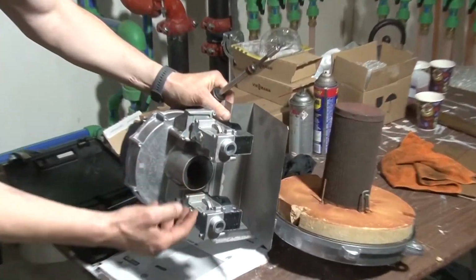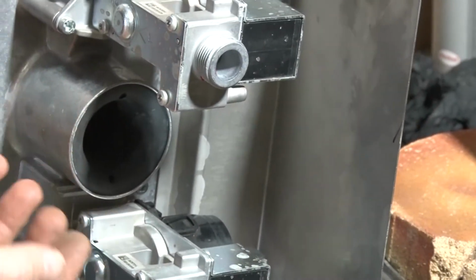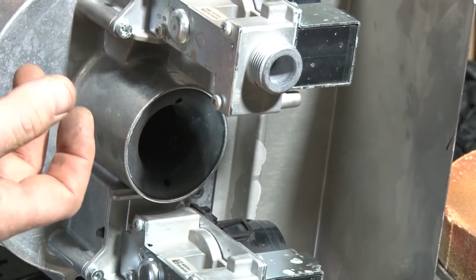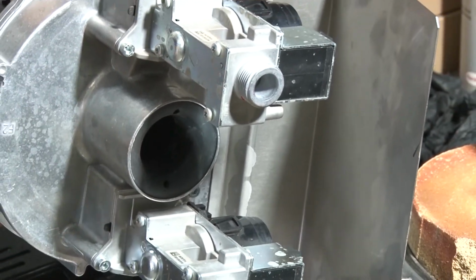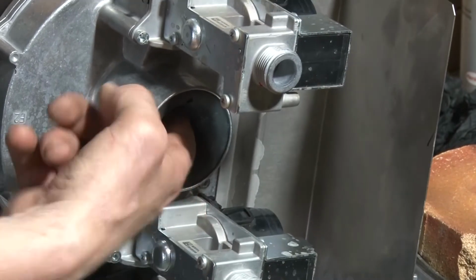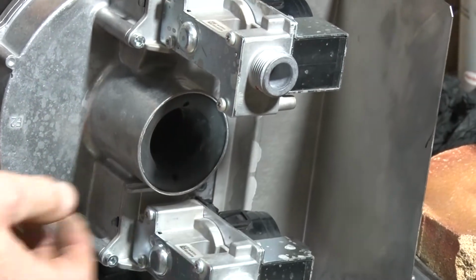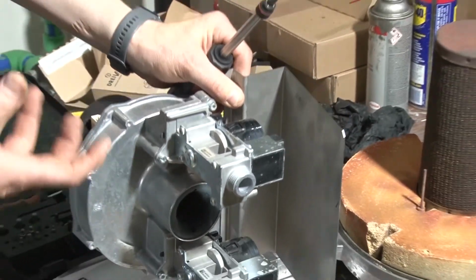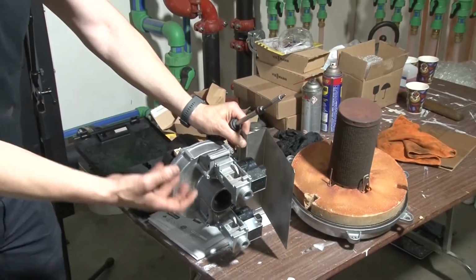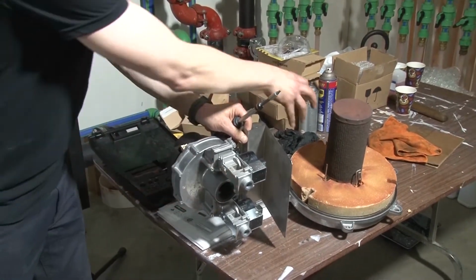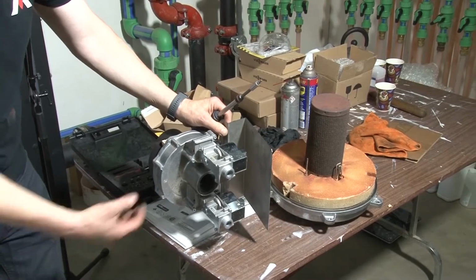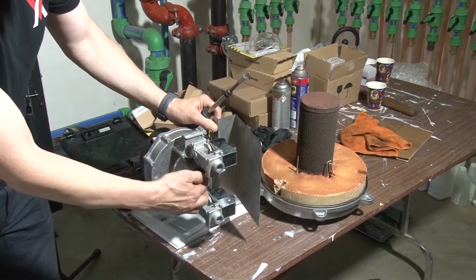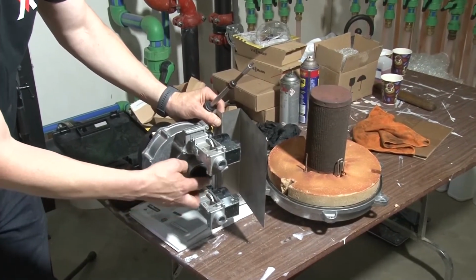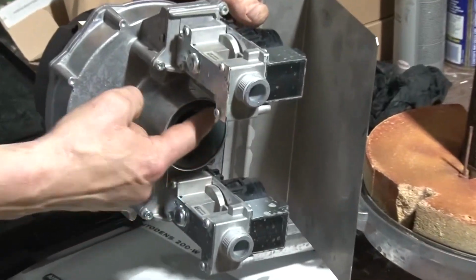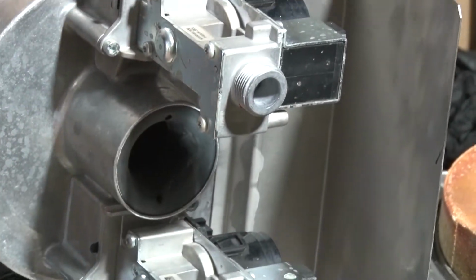Right. This is where your combustion air and your gas are basically starting to mix inside of the burner. So this is the first spot inside where the gas is entrained into the air as it comes through the venturi. That creates a turbulence that mixes. We call it a premix burner because it's starting to mix down here before it actually lights off at the burner here. All that stuff is going on. We want to make sure the condition of this is in good shape, so it's not cracked, it's not melted, there's no issues with it. This one looks in good shape.